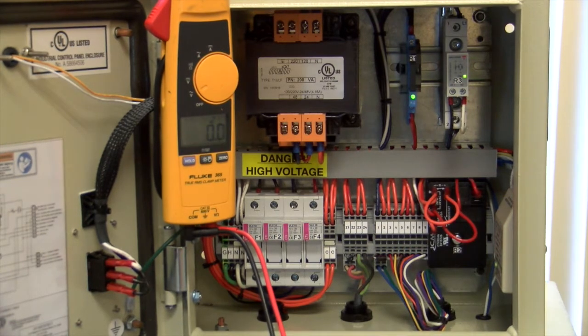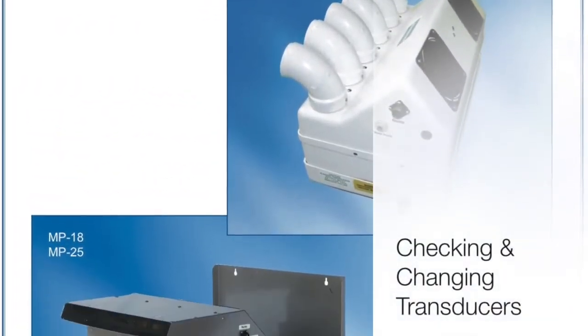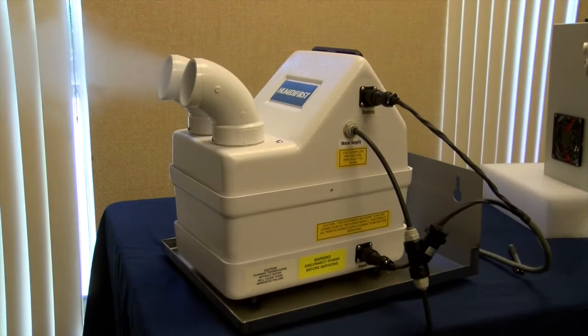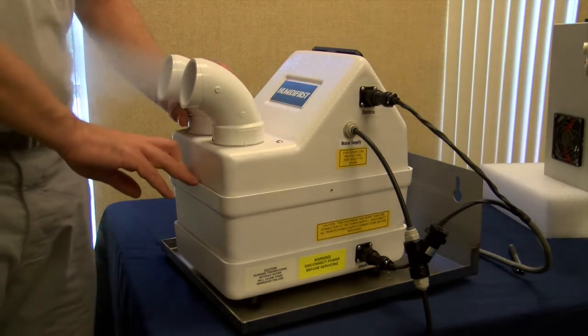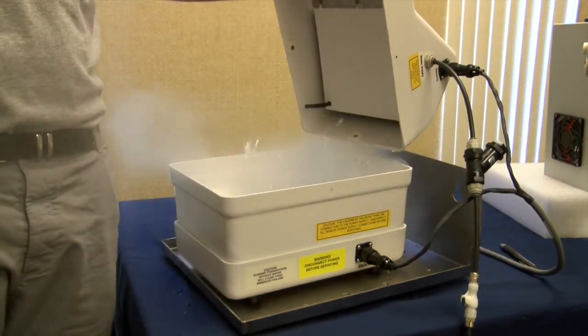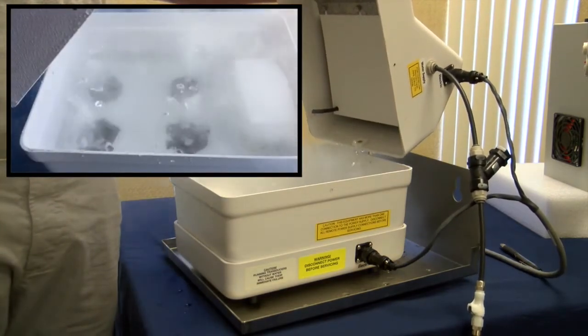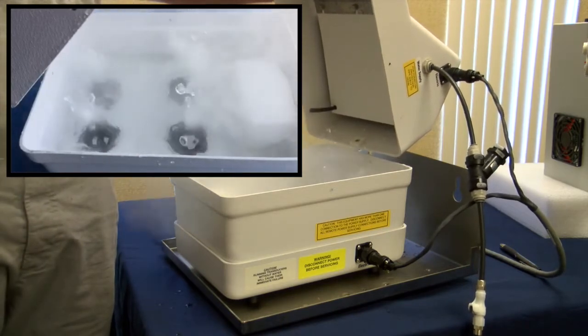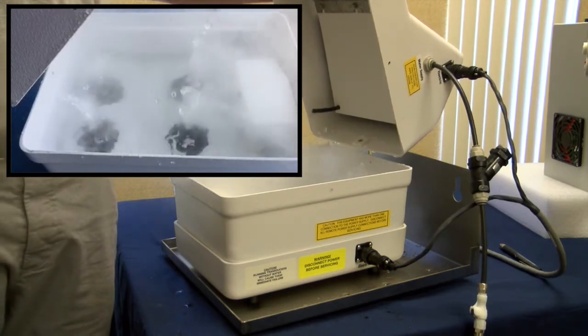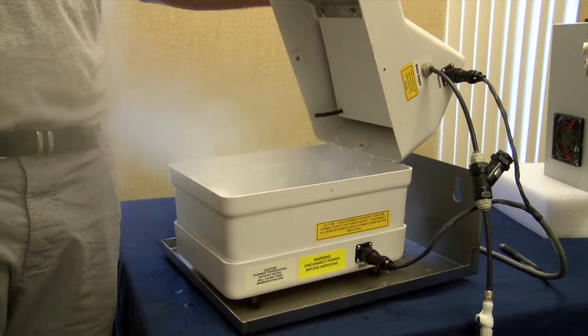If our humidistat is in the off position, both R1 and R3 will turn off. When R3 is lit, our unit will be calling for humidity, meaning our unit will be in the on position. To check to see if all of your transducers are working properly, simply remove the set screws, lift up the lid, and make sure all of your transducers are firing. The transducers are working properly if you see a 1 to 2 inch fountain over each of the transducers. If you don't see any fountain over the transducer, you probably have a bad transducer.